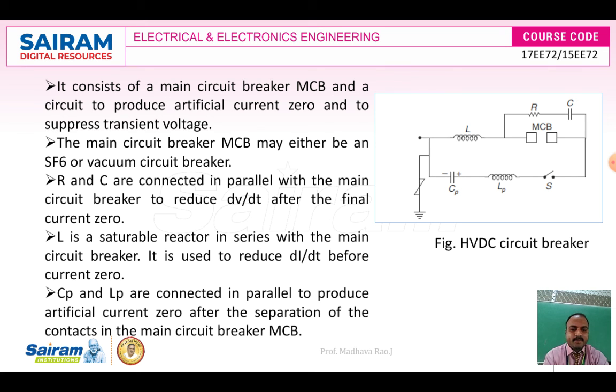CP and LP, a parallel capacitor and a parallel inductor, are connected to produce artificial current zero after separation of the contacts in the main circuit breaker. You can see in this diagram, to produce artificial current zero, the contacts in this main circuit breaker separate. Once the contacts are separated, the artificial current should become zero. That is why LP and CP are connected in parallel. Okay, so this is about the HVDC circuit breaker.